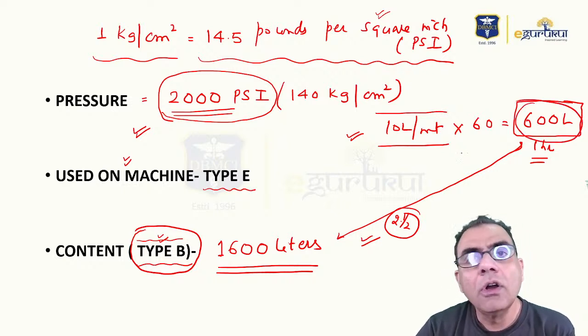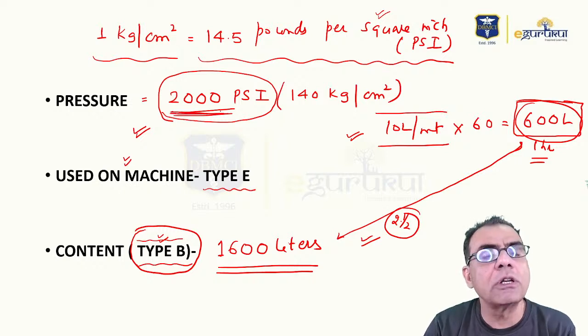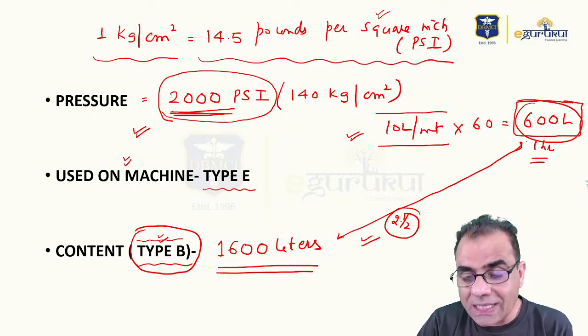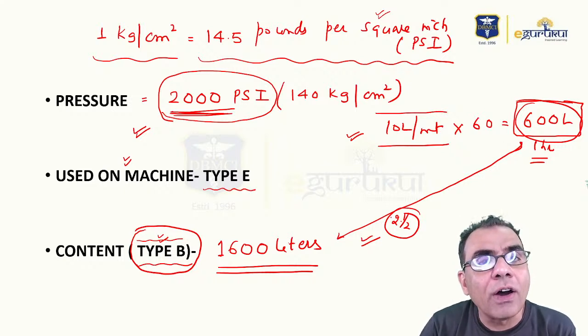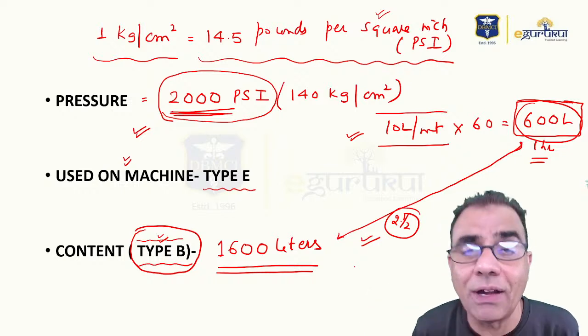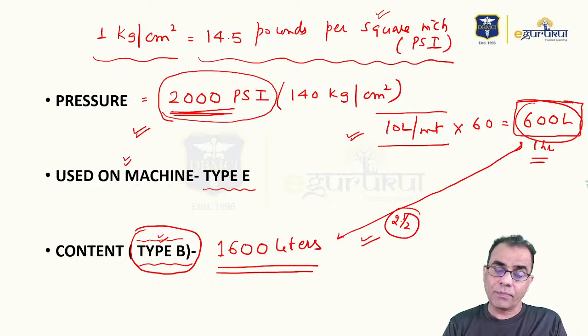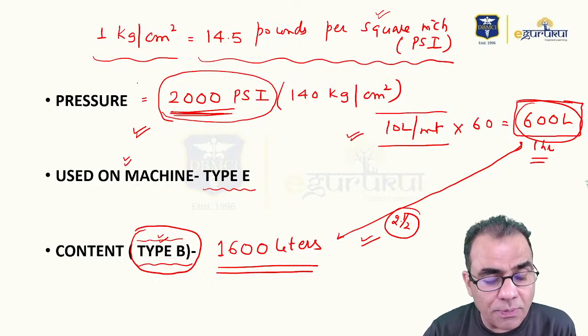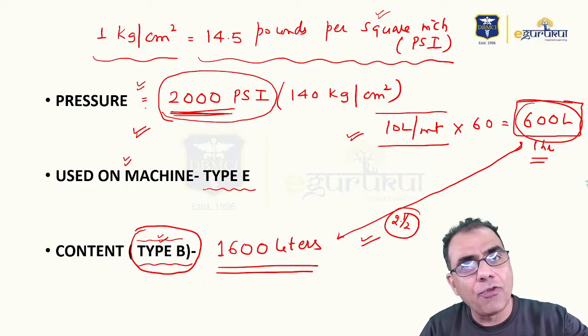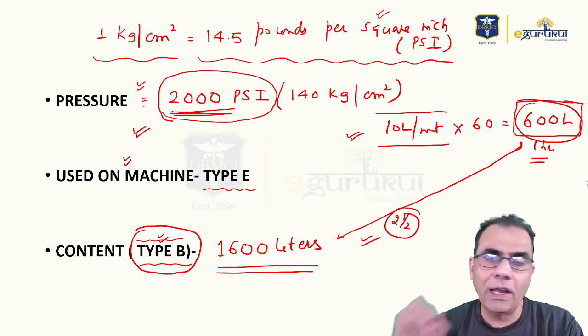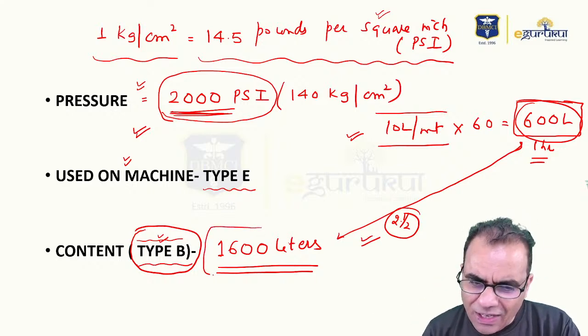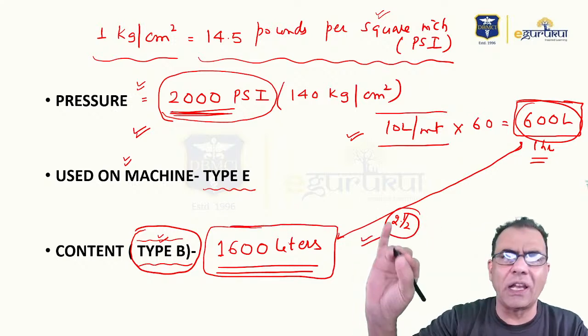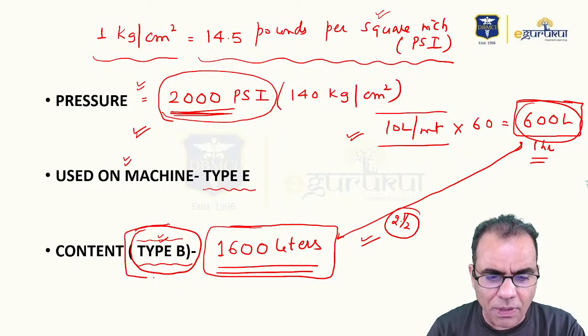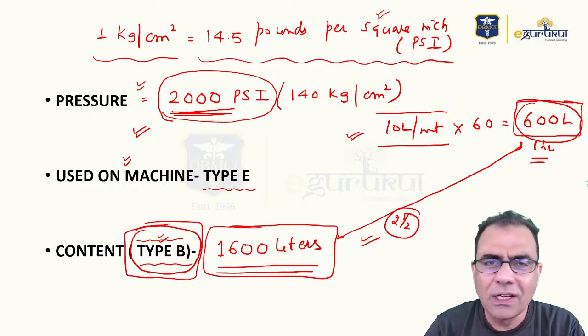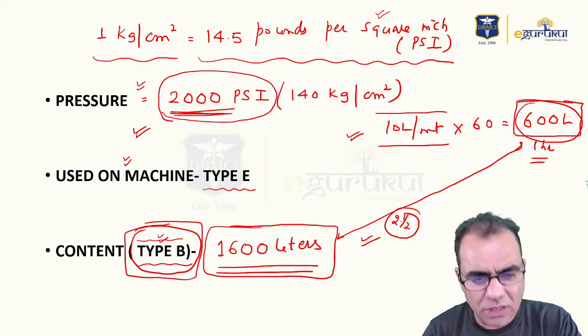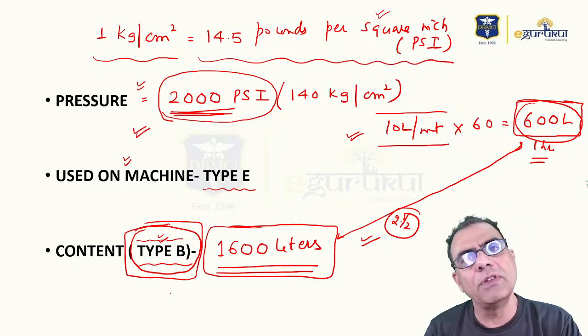So not even 1 hour. Or if they say the pressure is 1000 psi, which means half full, that means this cylinder is going to last around 1.5 hours. So these kinds of questions are very commonly asked nowadays regarding the consumption of oxygen. I hope now it is clear. A full cylinder is 2000 psi. If they give 1000, it means half full; 500 means one fourth full. So accordingly you can calculate. And even if they don't say which kind of cylinder you are using to transport a patient, assume that it is type B and the content will be 1600. That's it, because they don't ask about other types of cylinders, because in ambulances and in wards it is type B which is being used. Correct.